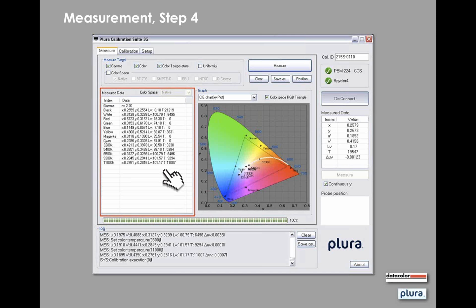How often do you recommend that the PBM or the other displays be recalibrated? We normally recommend about once every 12 months. And of course, that's probably going to depend on how much use the monitor is getting. So if it's got a lot of hours on it, then you would probably recalibrate sooner. Well, every 12 months is really based on it going almost 24/7. So if you didn't use it as much, it might not be as necessary. But that's the nice thing about this Spyder Elite, the Spyder4. With our calibration suite, you don't necessarily have to calibrate the monitor every time you plug this in. You can always just do a quick 5 or 10 minute measurement whenever you determine you would like to, just to see where it's falling.